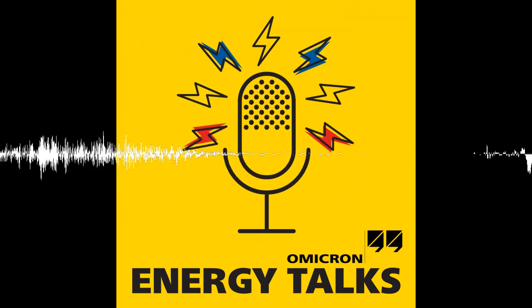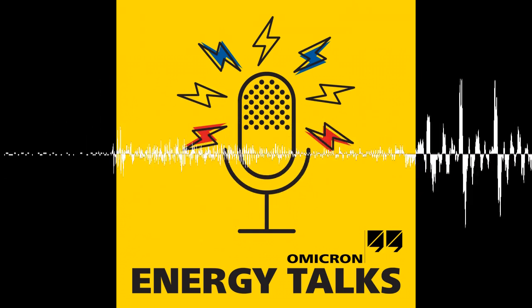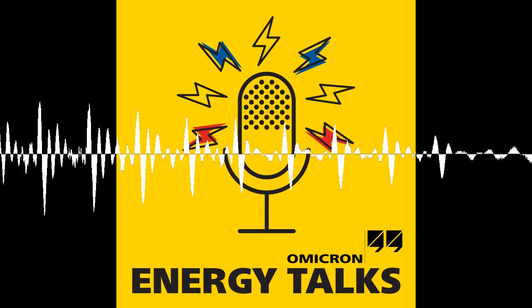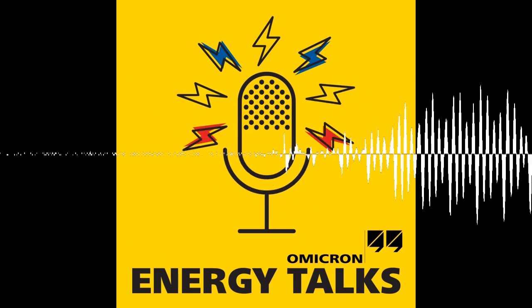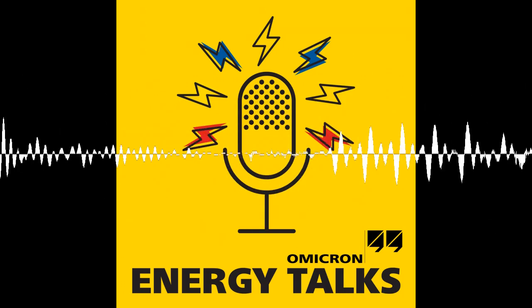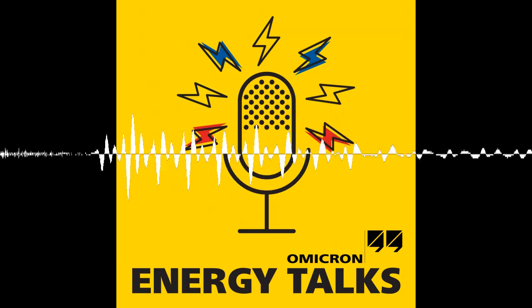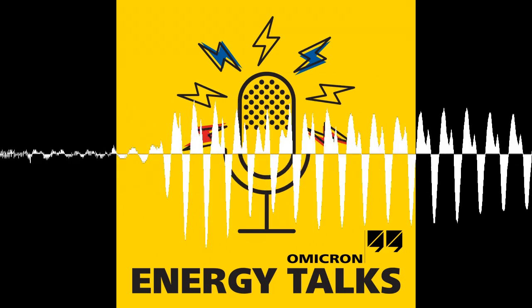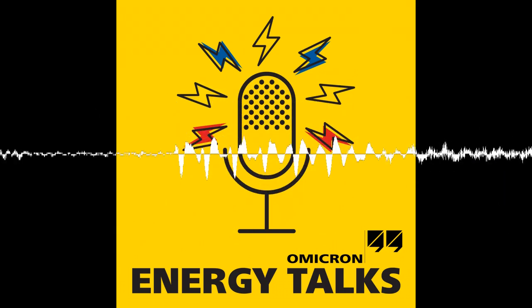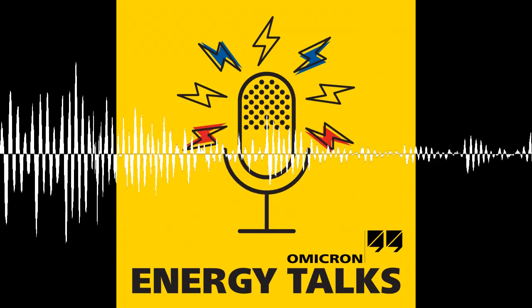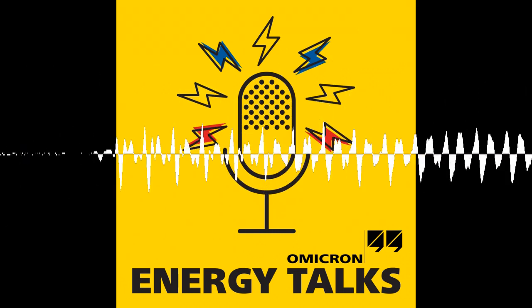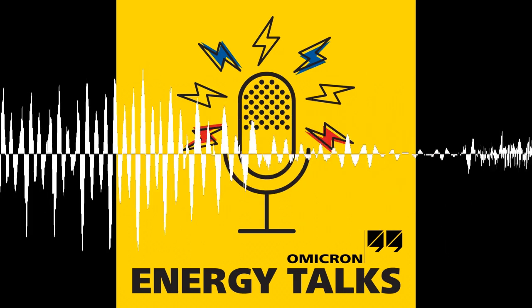What are the key aspects of the Omicron StationScout testing solution that make these improvements possible? It's really about how you start such a test. You first of all want to see what is happening inside. So we started with the visualization of the substation automation system, who is talking to whom, how the IEDs, the intelligent electronic devices, are communicating together.